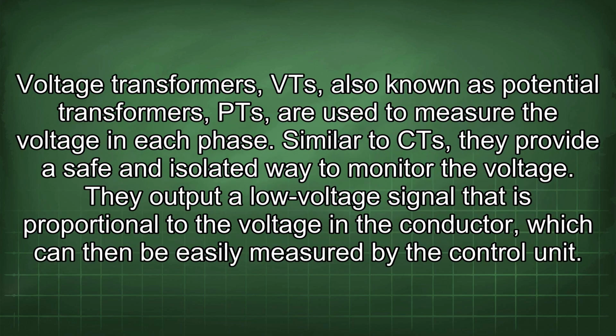Voltage transformers, VTs, also known as potential transformers, PTs, are used to measure the voltage in each phase. Similar to CTs, they provide a safe and isolated way to monitor the voltage. They output a low voltage signal that is proportional to the voltage in the conductor, which can then be easily measured by the control unit.